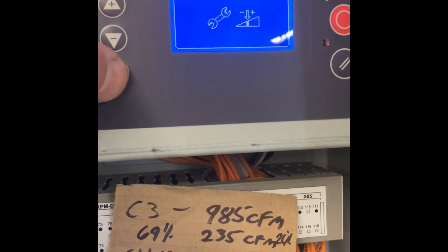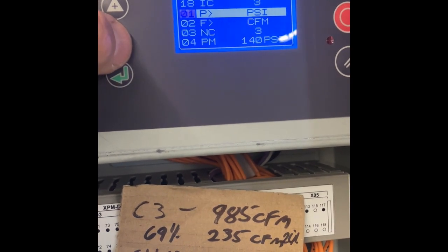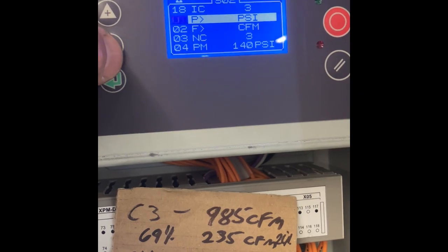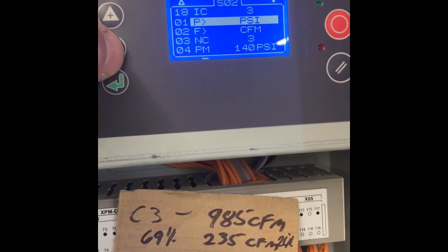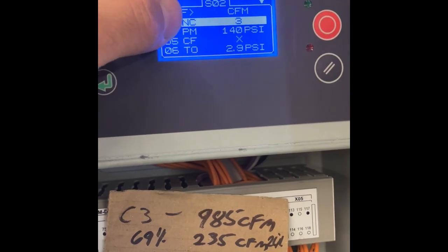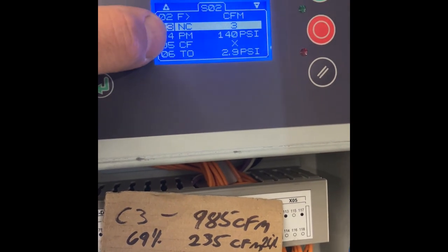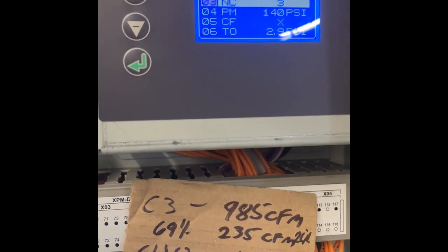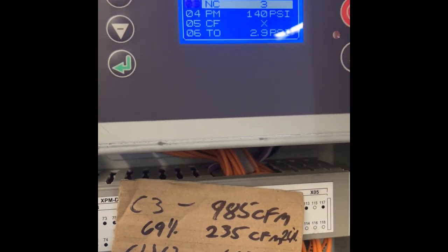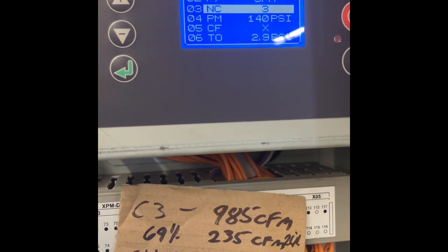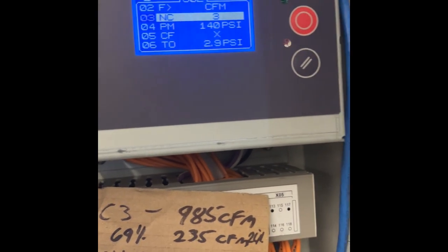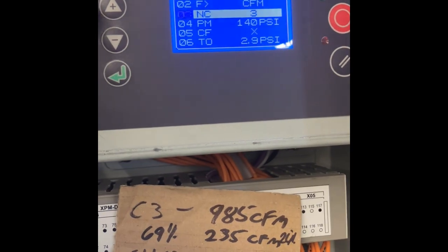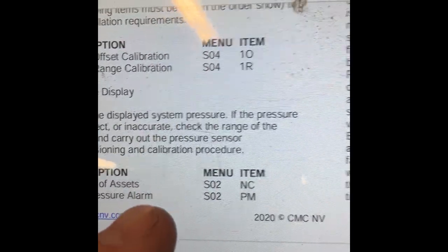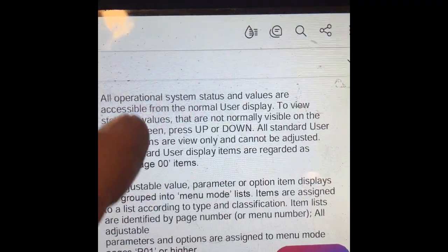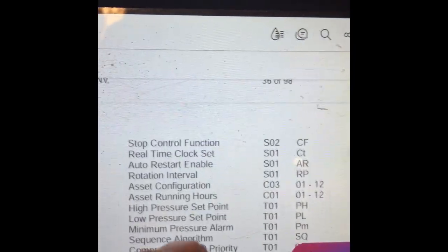So S02, hit enter, and this is where this thing comes default for PSI, CFM. So if you want to change that here, you can. Number of compressors in my system is going to be 3. Pressure max, they're all rated for 135. I usually like to go about 5 over whatever the rating is. So we're not going to run anywhere near that though.